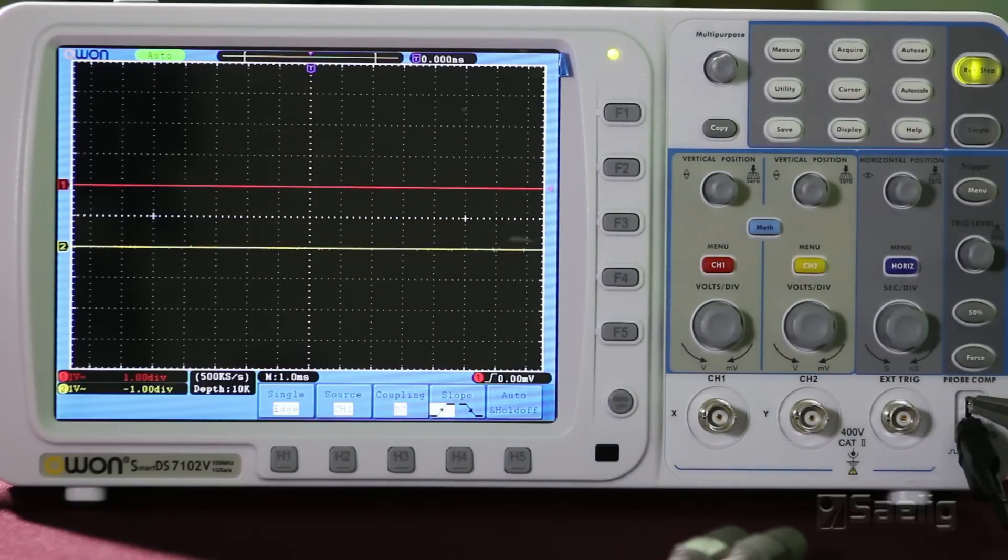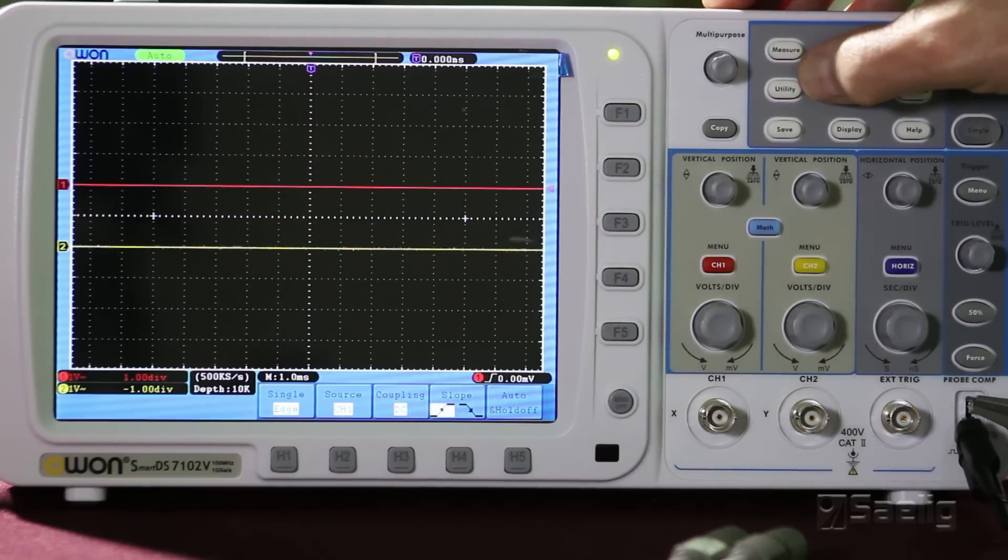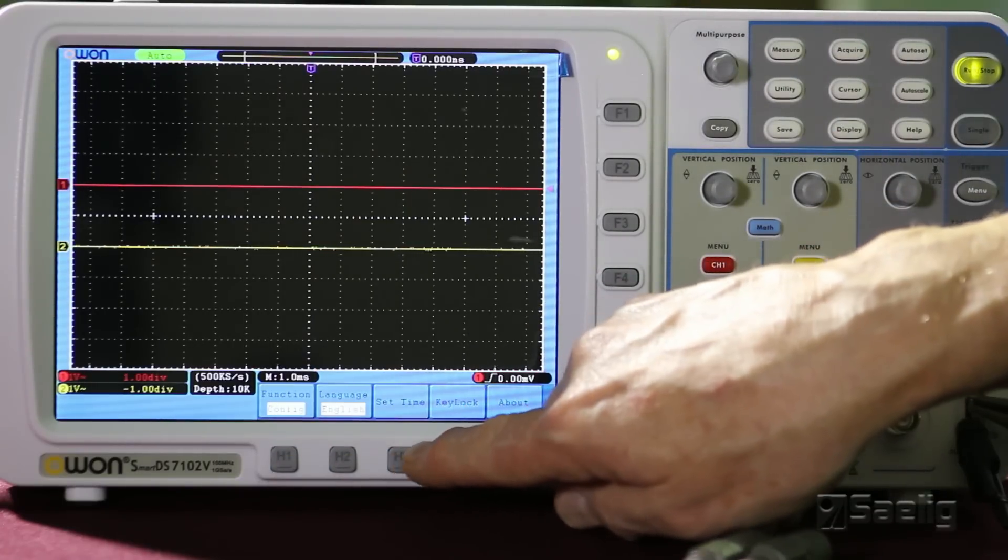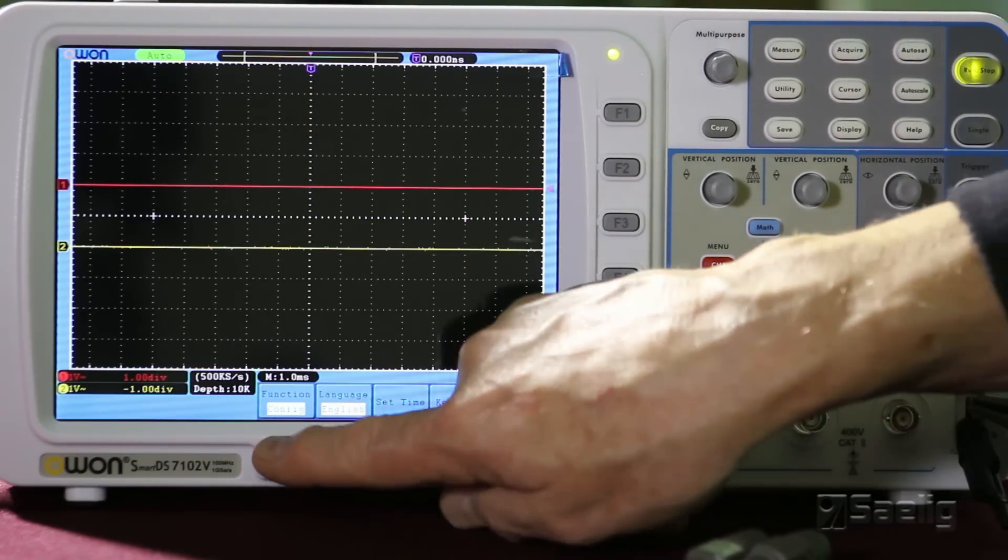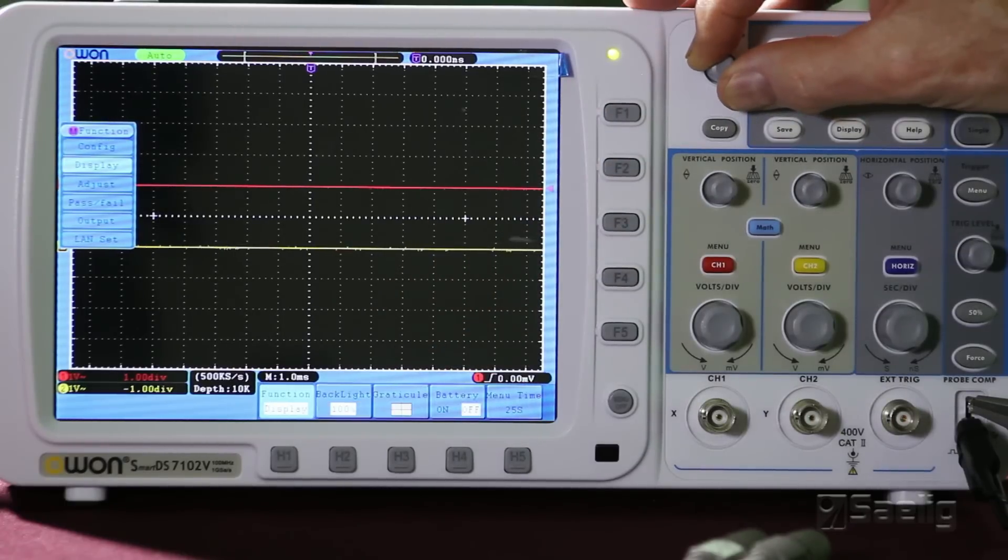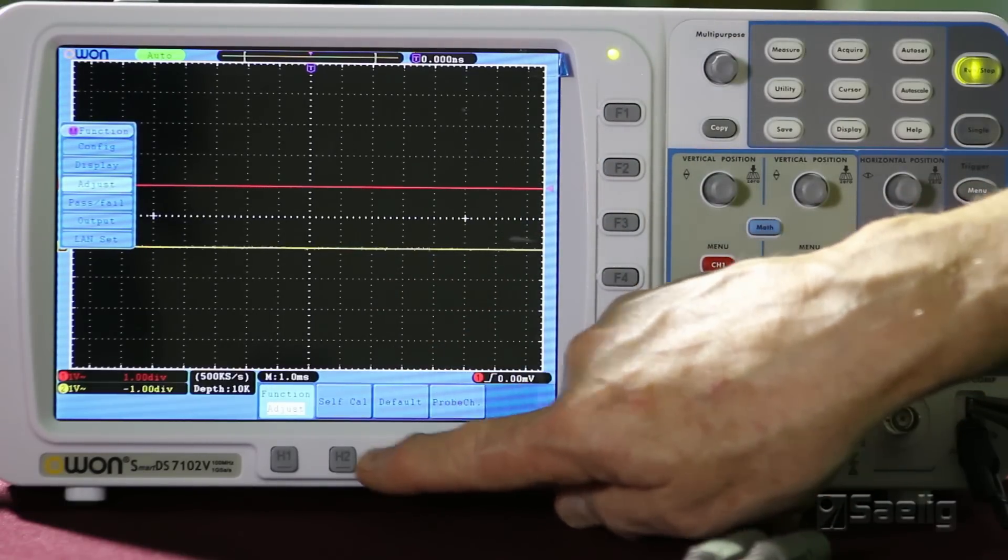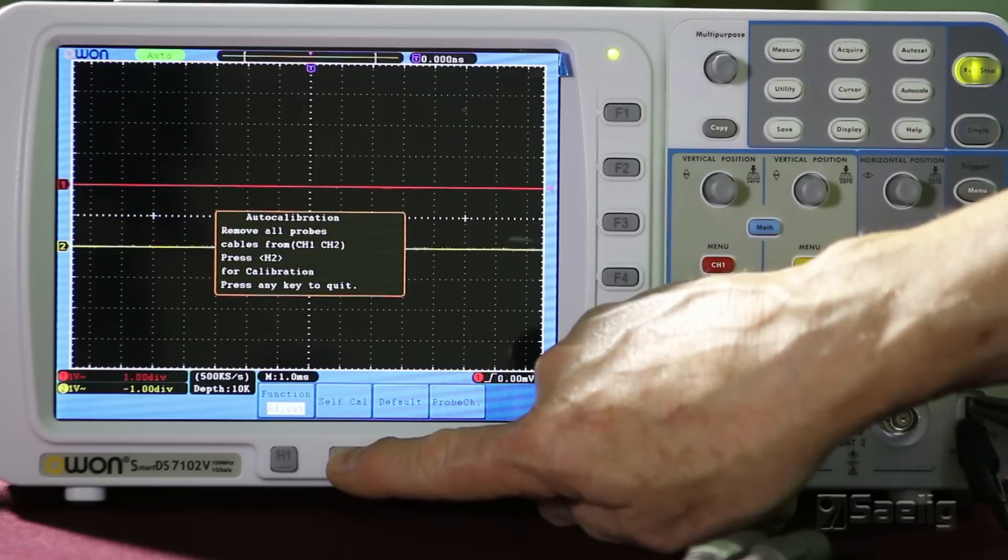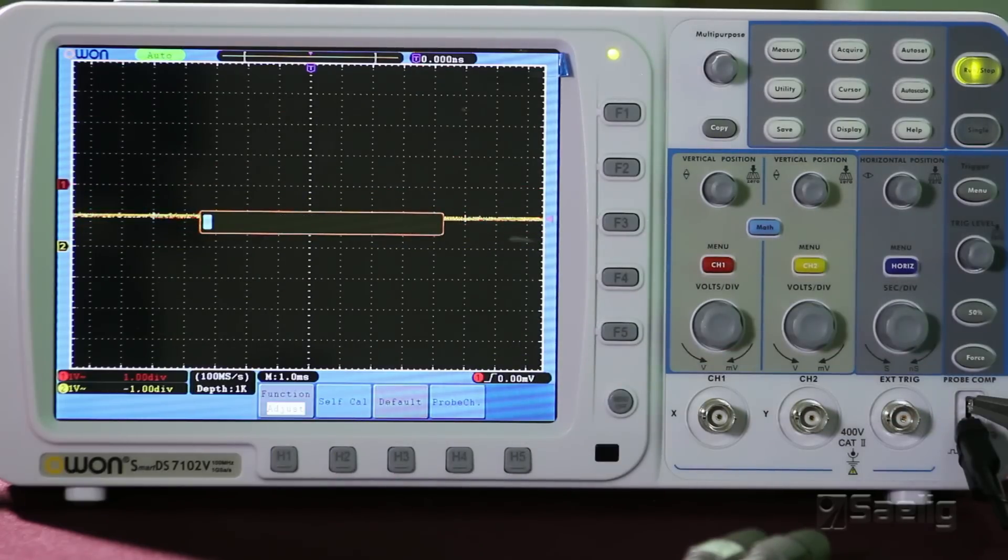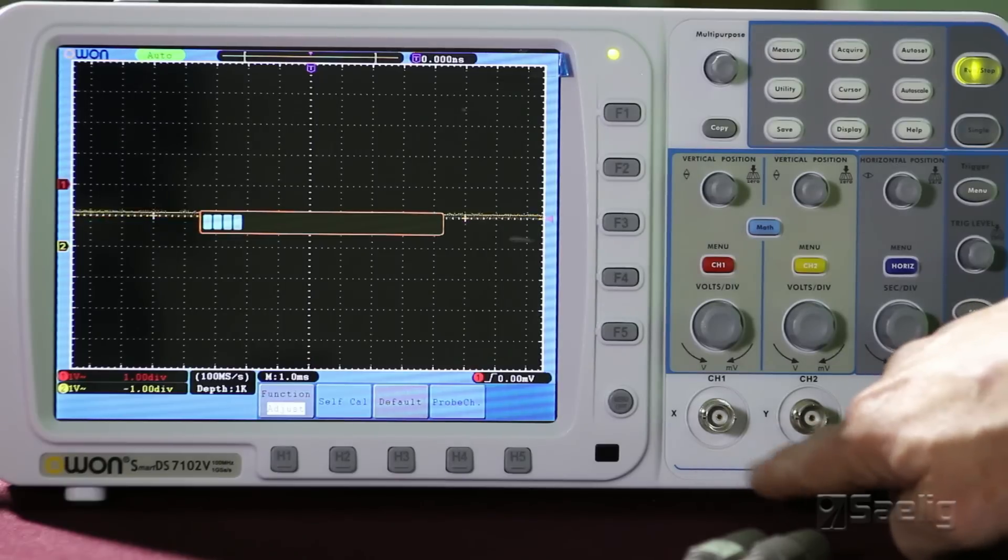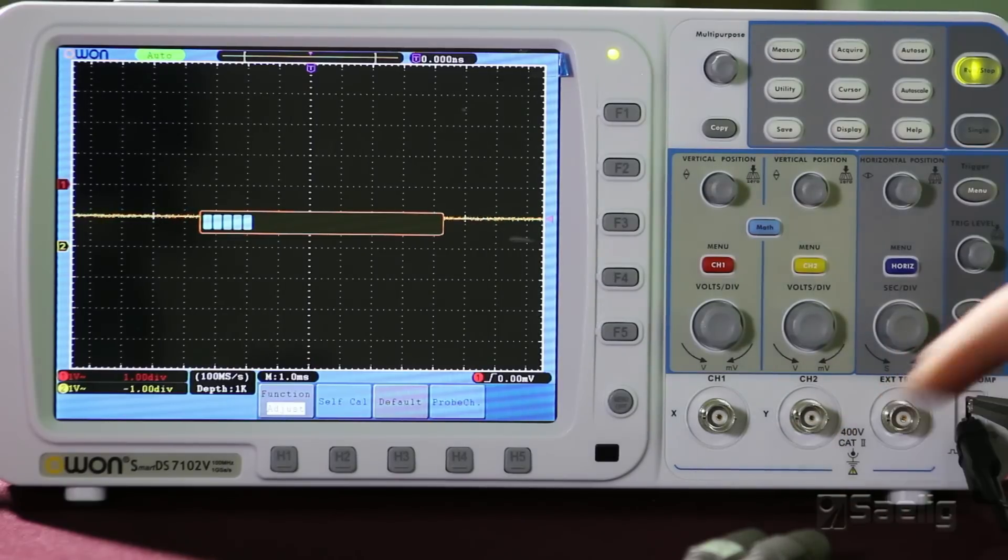So, anyway, the next thing to do is to make sure that the scope can pass its own self-calibration program. And again, that's underneath the utility key. So we're going to just find it real fast here because we ended up setting factory defaults. Here it is here, self-cal. And, of course, when you do this, you don't want to have anything attached to the channel one, channel two front end inputs right there.